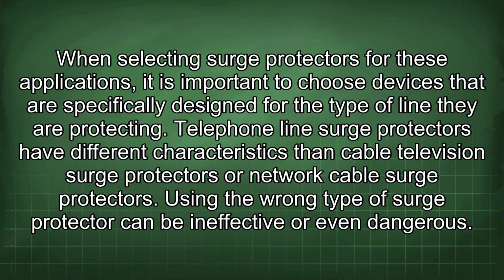When selecting surge protectors for these applications, it is important to choose devices that are specifically designed for the type of line they are protecting. Telephone line surge protectors have different characteristics than cable television surge protectors or network cable surge protectors. Using the wrong type of surge protector can be ineffective or even dangerous.